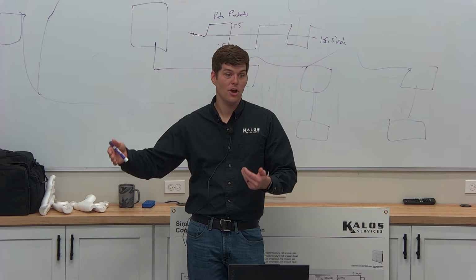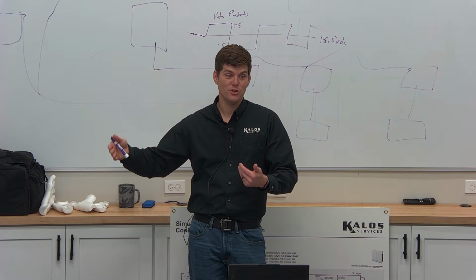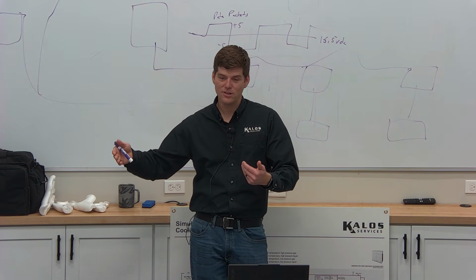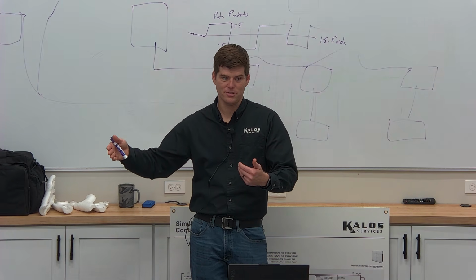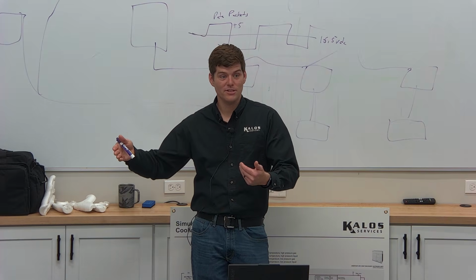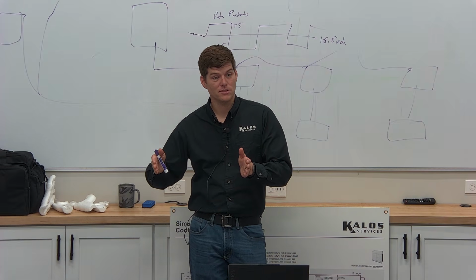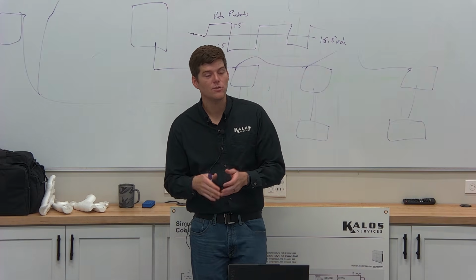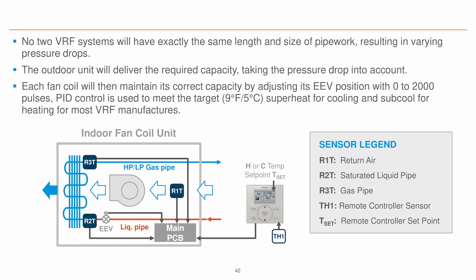Still not close. Open up 100 pulses. Superheat goes down to 15 degrees. Still not there. Open up another 100 pulses. 10 degrees. Okay. Close off 15 pulses and it starts to dial it in. And so it's constantly doing that. And the way that it does that is by the temperature sensors on the indoor unit. Why is it important to know that?